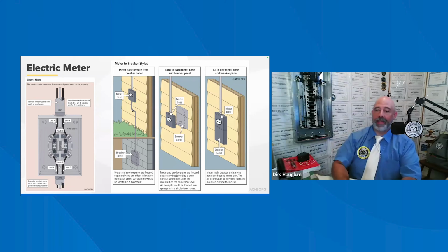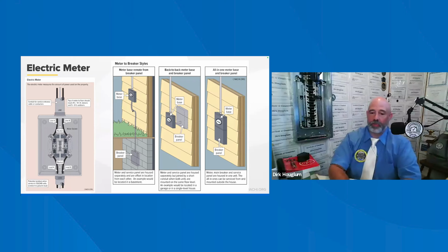All-in-one systems. In many areas, especially in the US, you will find the meter, main breaker, and panel all together in one unit mounted on the outside of the house. In other setups, you might see the meter outside, with wires running inside to the main panel, which includes the main breaker and branch circuits. Even though people often call it the main breaker panel, that's just a common term. It's not an official code term. And again, we're not code inspectors, we are safety inspectors.